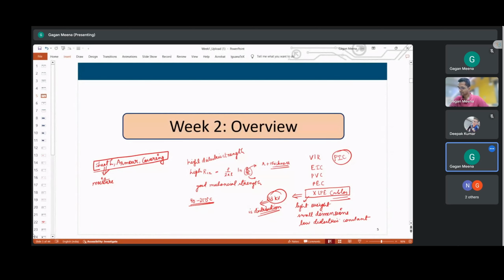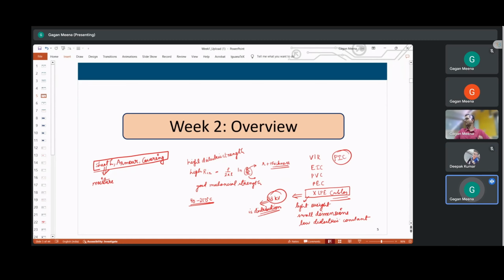I think sheath is used to protect the conductor so that no type of chemical reaction happens from the soil, I think. Yes, that is correct in one sense. It is provided over the cable, over the conductor on which we have insulation, so that it is covered, so that moisture may not be able to affect the cable. And it also protects the insulation from mechanical damage, because insulation is very important.